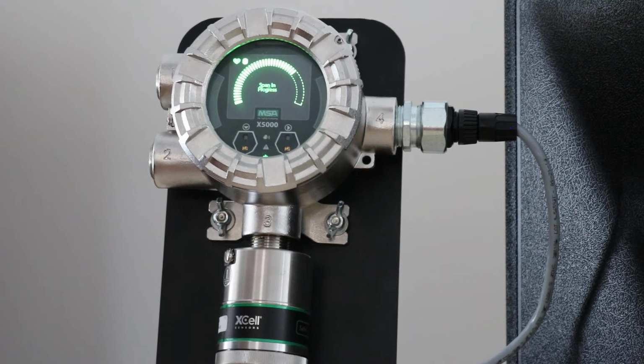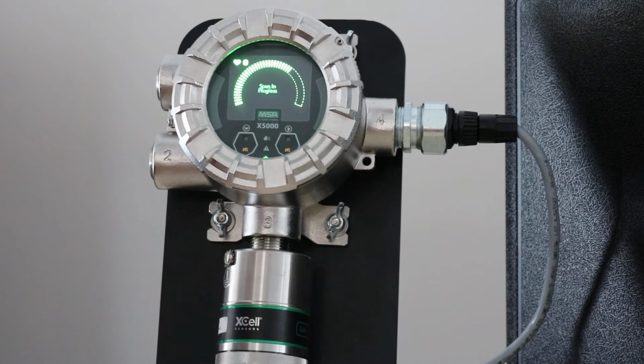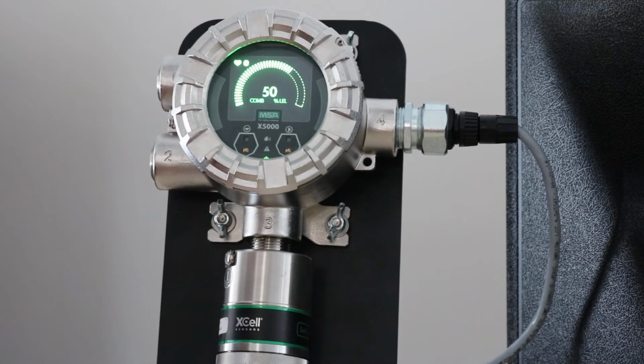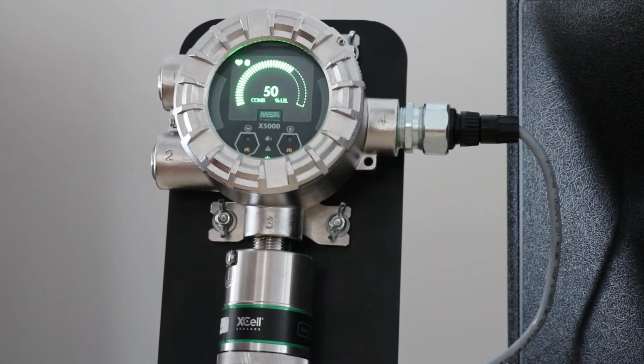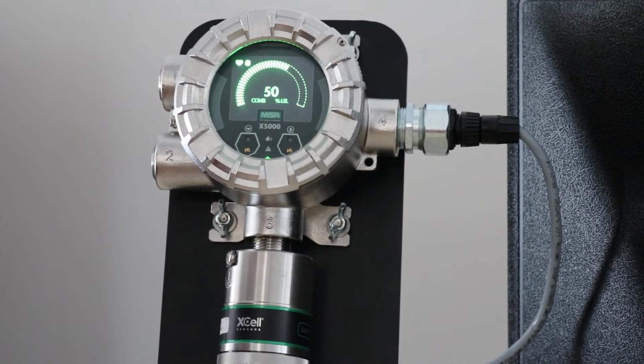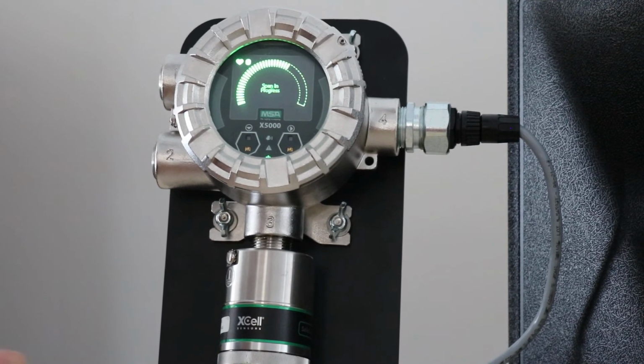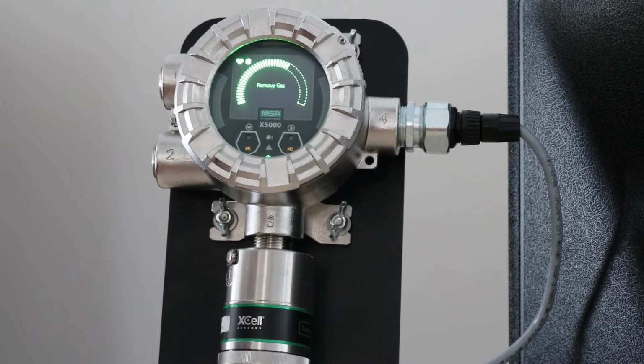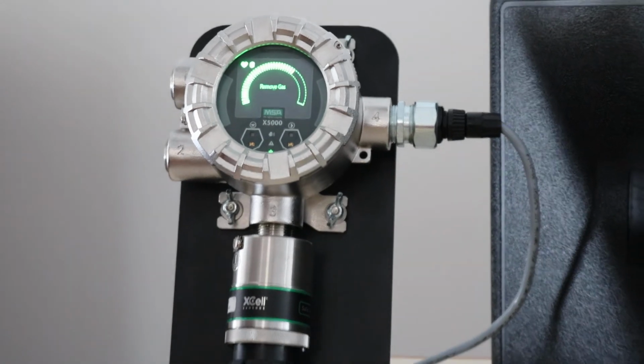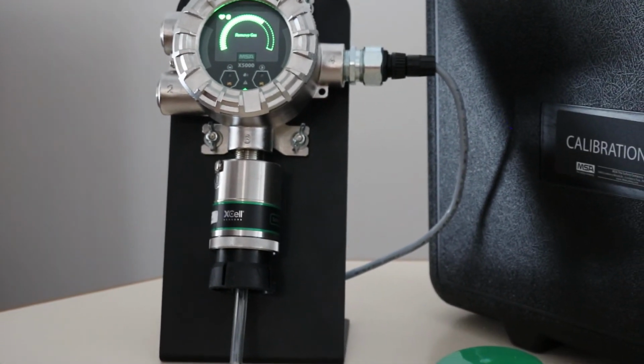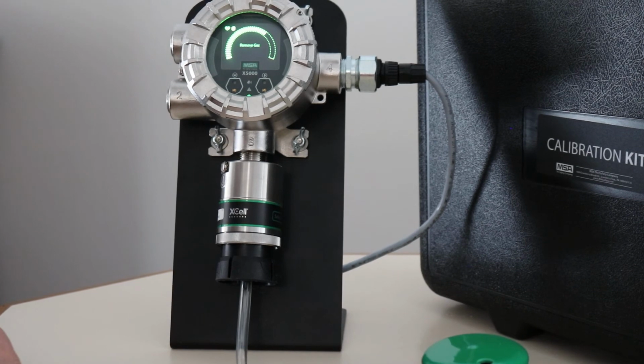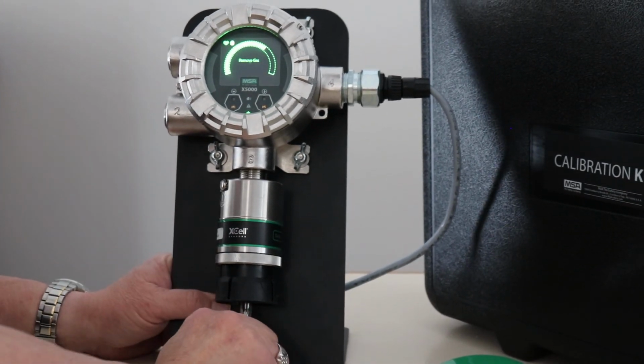So as we wait for this to count down, once it gets there, you will see, I hope anyway, that calibration passed. It will give you a display that tells you what it found it at and what it left it at. And in this case, it would be 50% is what it should leave it at when it's calibrated. Remove gas, it says. Okay, so we remove the span gas. So we shut our gas off at the cylinder and we remove the tubing.